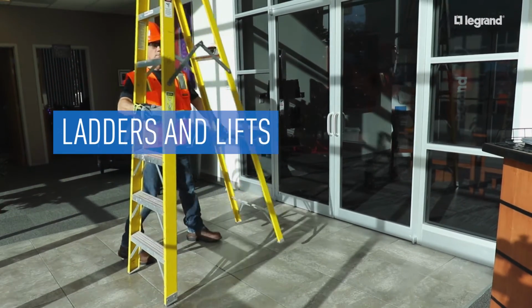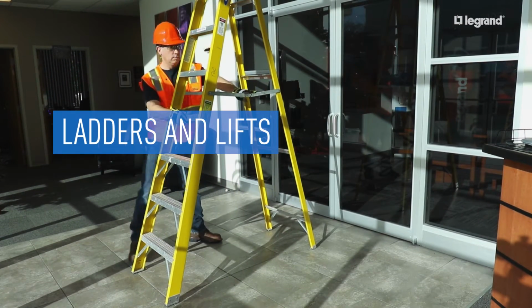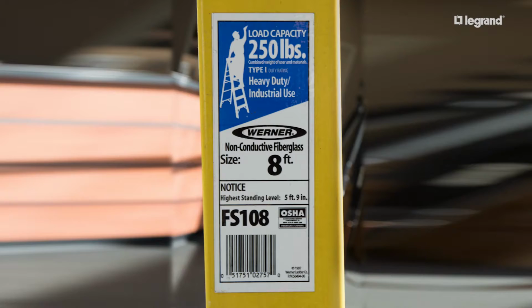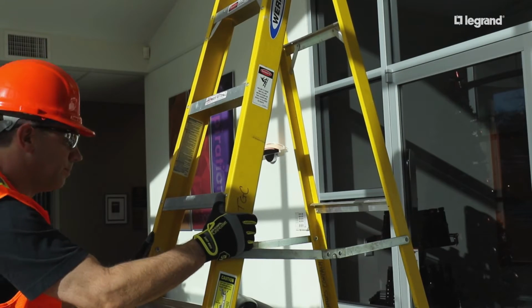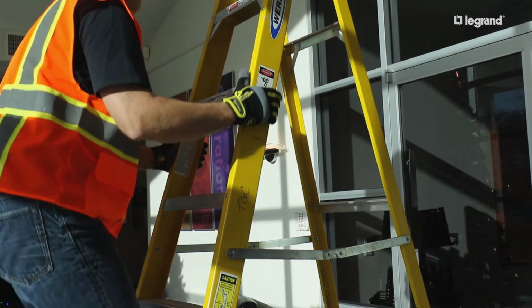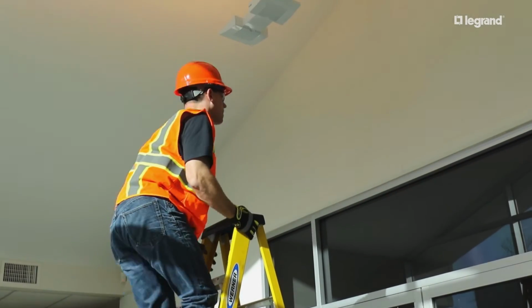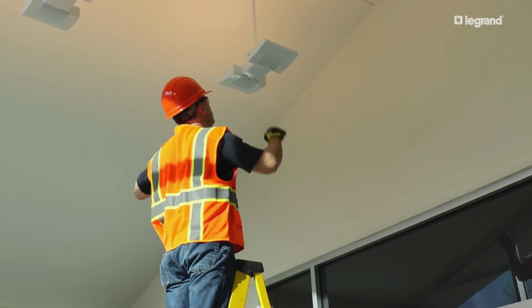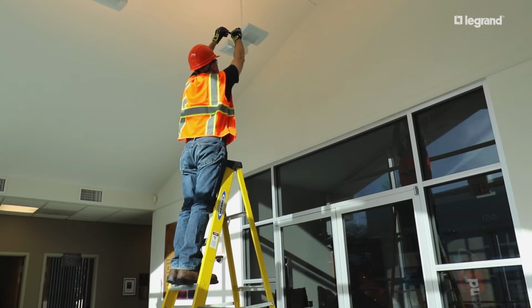Always use ladders with non-conductive components near electrical work. Do not exceed the duty rating of the ladder. Never stand on the top rung or step of any ladder. When climbing ladders, keep 3 points of contact: 2 feet, 1 hand, or 1 foot, 2 hands.